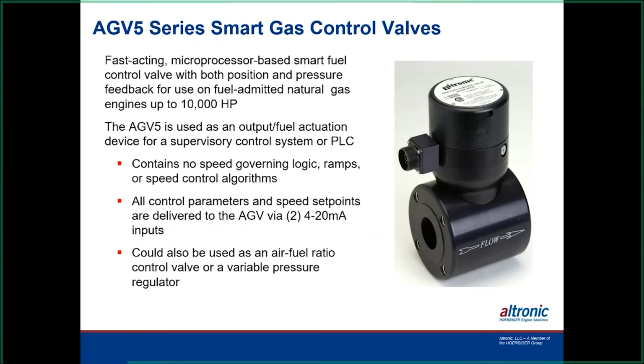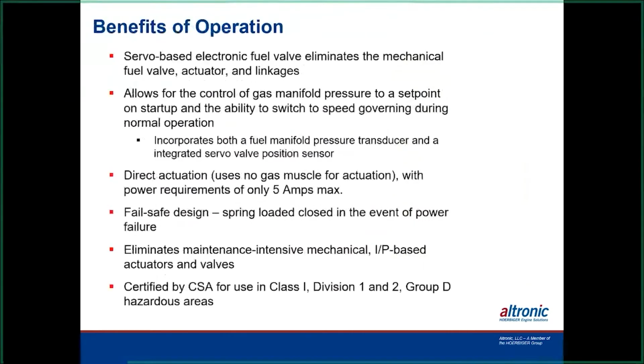And it's probably the one used mostly in the field. They have companies with the PLCs or some type of supervisory control system in it. And a servo-based electric fuel valve eliminates the mechanical fuel valves, actuators, and linkages.